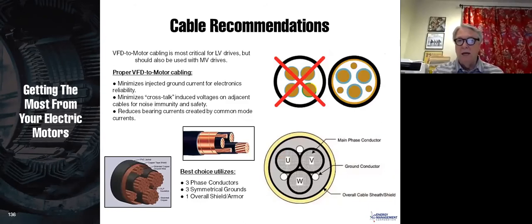In any case, let's take a look here. Now, they recommend, if you really want the Cadillac, that you build your cable like this. First of all, you don't use 3 separate wires. You use one cable that has the 3 wires in it. So you can see the first thing we do is we take the UVW or the L1, L2, L3, whatever, and they are in a triangle pattern. What that does is keep the capacitance between any 2 of the phases the same, and that will keep you more balanced.